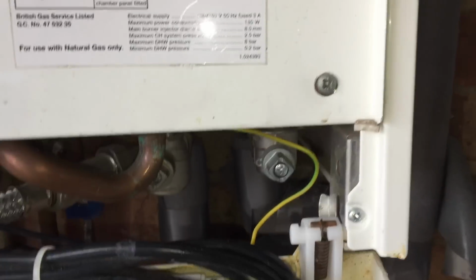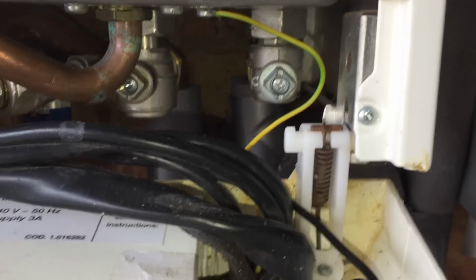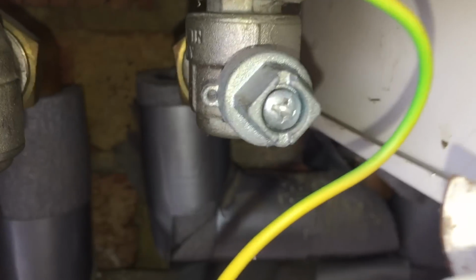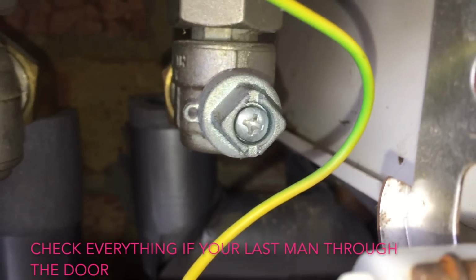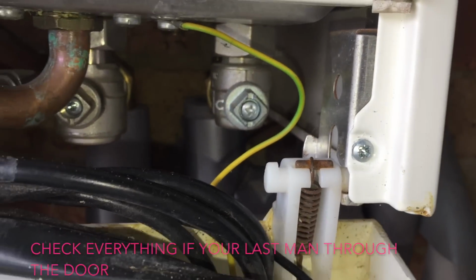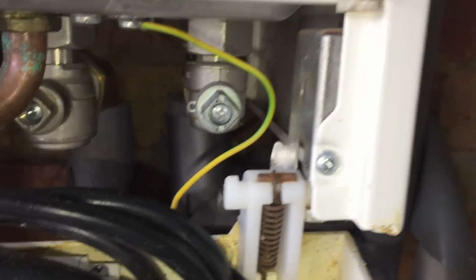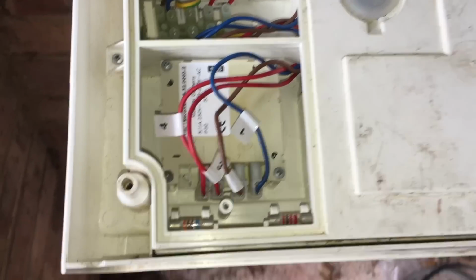Right, I wonder why this would only short cycle on heating. As I'm tidying up, I've had this on test, and that valve was closed. Not all the way, but a lot of the way. So I've just opened that, and the boiler's running a bit harder now. I can hear it for heating, so the heating's now all going to be coming on in there. All back together.